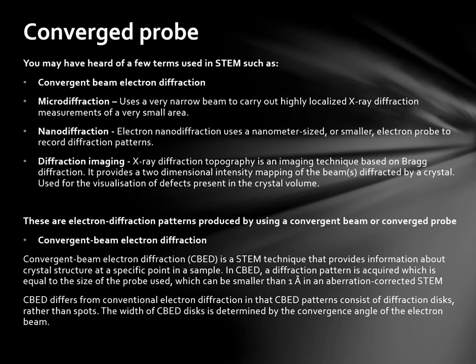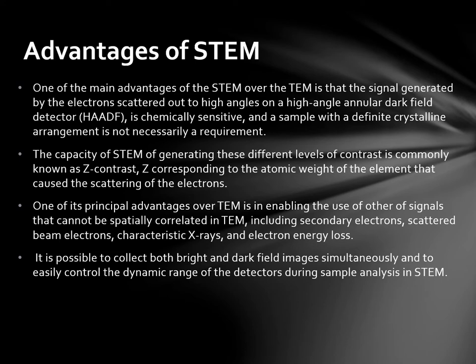One of the main advantages of STEM over TEM is that the signal generated by electrons scattered out to a high angle on a high-angle annular dark field detector is chemically sensitive, and a sample with a definite crystalline arrangement is not necessarily a requirement. The capacity of STEM to generate these different levels of contrast is commonly known as Z-contrast, Z corresponding to the atomic weight of the element that caused the scattering of the electrons. One of the principal advantages over TEM is that STEM enables the use of other signals that cannot be spatially correlated in TEM: secondary electrons, backscattering electrons, characteristic x-rays, and electron energy loss. It is possible to collect both bright field and dark field simultaneously and easily control the dynamic range of detectors during analysis in STEM.